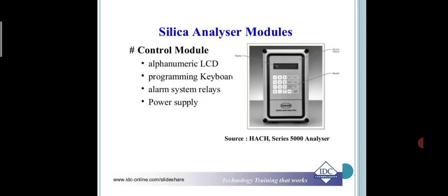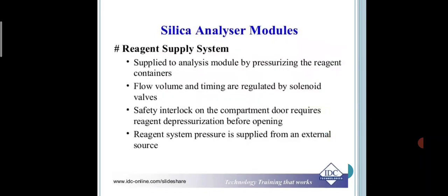Silica analyzer modules. Here we see that one of the components of the silica analyzer modules is the control module. This is one of the very important components in a silica analyzer. The alphanumeric LCD, programming keyboard, alarm system relays and power supply are all contained in the control module.